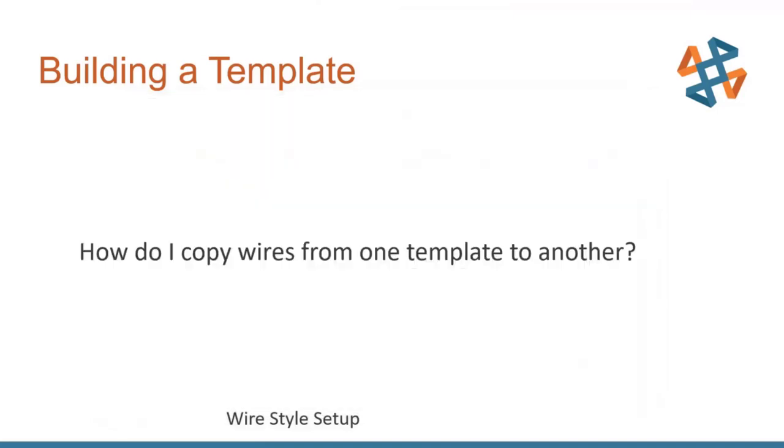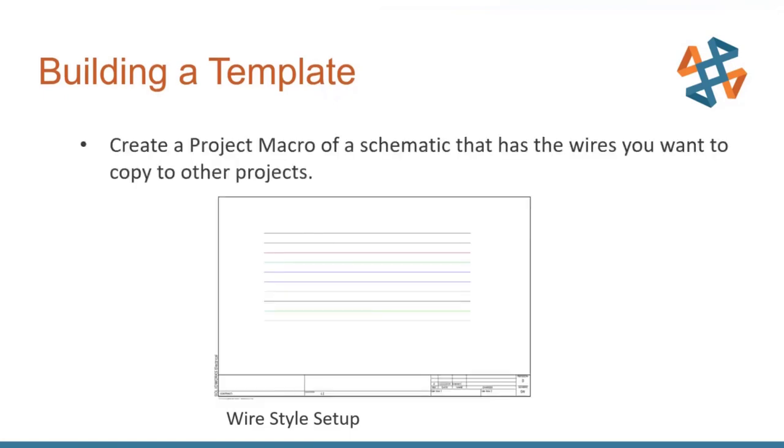Well, I mentioned that wire styles are project specific. Let's beg the question, is there a way to add wire styles from one project to another? What you can do is you can simply copy one over, copy a wire over from one project to another. That'll add it into that new project. You can always start from a template. That is probably the best way to do it. But realistically, you'll probably be adding wires down the road. So what do you do? Well, you can also library your wire styles by using what's called a macro. And a macro is simply a collection of any information that you want and storing that information as its own library entity. So you can literally group, maybe you have a bunch of 18 gauge wires. You can draw those on a schematic and you can save that whole schematic as its own library entity and pull that into any project that you choose, thereby adding all those wire styles to that project.